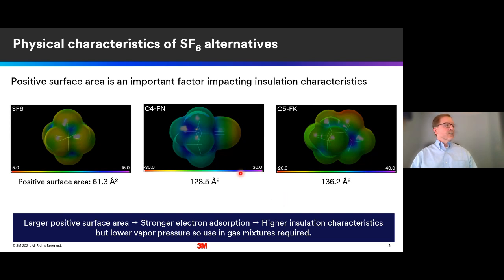So here we compare the two alternatives Renee mentioned, the C4FN and the C5FK, compared to SF6, and you can quickly see that these are significantly larger positive surface areas, which means that it actually will have a higher electron capture capability and results in higher dielectric breakdown voltages on a molecule per molecule basis relative to SF6.